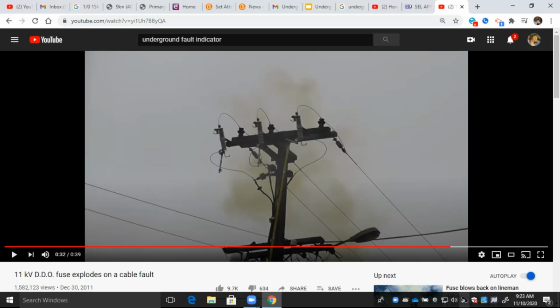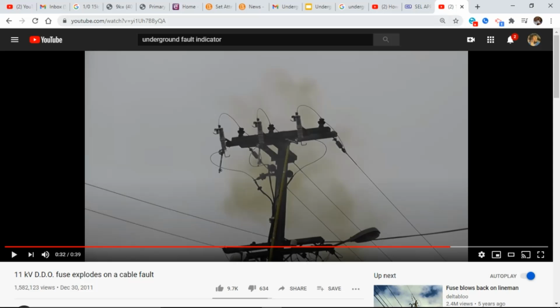Okay. All right. So that's that video right there. So let's go ahead and get into the second method. And this is going to be one of your test questions. There are two methods to finding underground primary faults in spans. One is, what's the first one we've learned about? You just said it, Cole Kennedy. High pot. I go from switch to underground primary, and then I would do what they call leapfrogging. I go to the first transformer test, second transformer test, third transformer test, on and on until I find the faulted span.